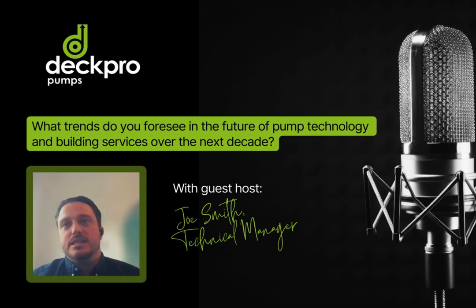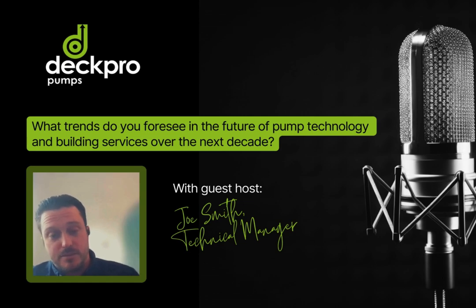So over the next 10 years, I would expect that efficiency will start outweighing budgets, or budgets will include efficiency to some extent. The cost of energy, although it seems to have come down a little bit, fluctuates so expensively at times that if we look at it as a fixed cost and you can actually bring your equipment cost down, it starts to balance out that you might actually be worth spending a bit more at the start on pumps, on drives, on smarter technology in the pumps. Even with a new IE5 rated pump, for example, you're going to get a 20% energy saving on an IE4 pump, and again on an IE3.